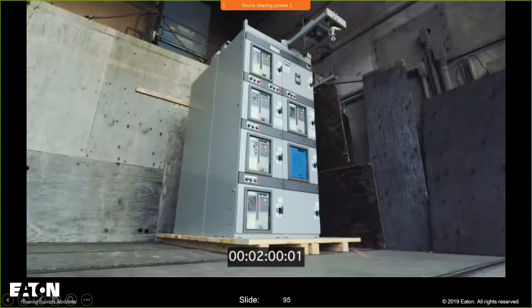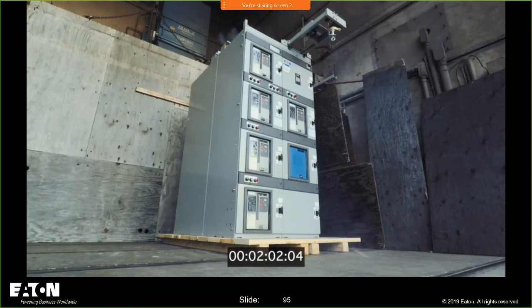All right, so I'm gonna pause this next portion of this video. All right, so let's take a look at what just happened. This little blue box right here is the arc quencher. This little relay right here is what senses. There's light sensors inside this box enclosure to sense the arc. When that relay senses the arc, it tells that blue box to activate, which causes a very low impedance. It's not a bolted fault, but a very low impedance, sucks the energy inside that blue box, basically, and it tells the main device to open. And all of that happens in 0.004 seconds.